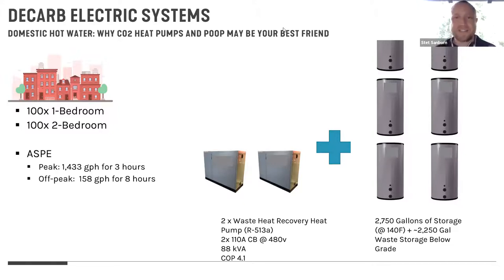And we did an exhaustive study of, oh, where can I pull power out? The service size on that building was so undersized that there wasn't anything I could do and still be code compliant, where an inspector wouldn't red flag me on day one. So yeah, all of the strategies are really about, what is your transformer capacity? What's your switchgear capacity? Don't touch it if you can. So that's my big call out, whether it's domestic hot water or adding space heating.